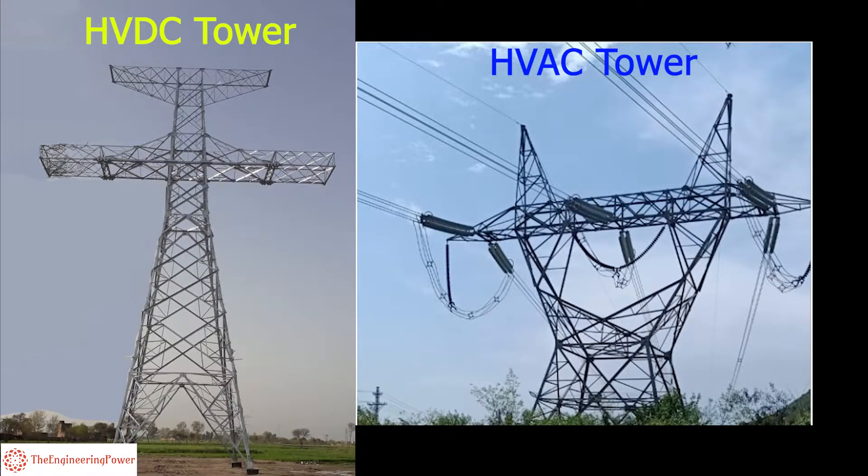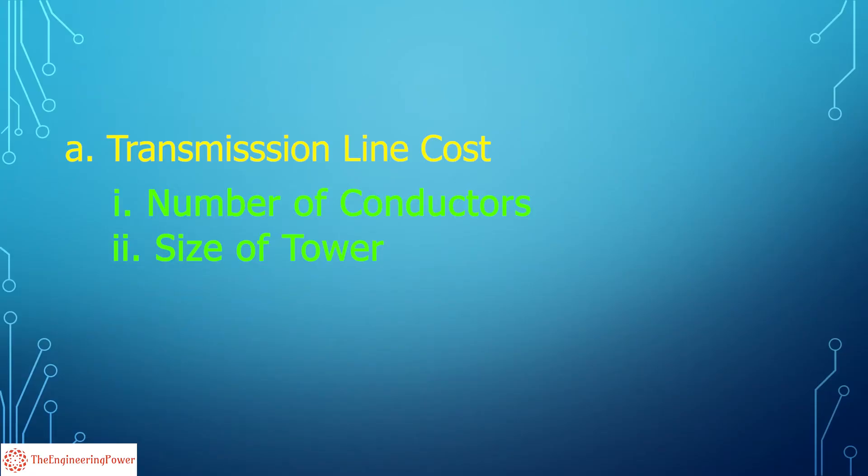DC transmission requires two conductors per circuit whereas AC transmission requires three conductors per three-phase circuit. Also the supporting towers used in HVDC system are smaller and require less right of way as compared to HVAC towers. So based on the number of conductors and size of towers, HVDC transmission line will cost less than an HVAC transmission line.